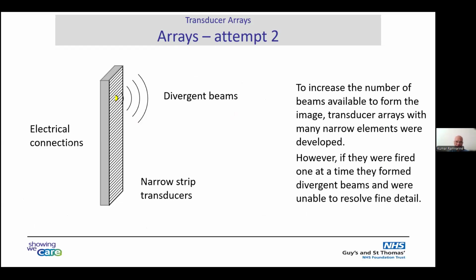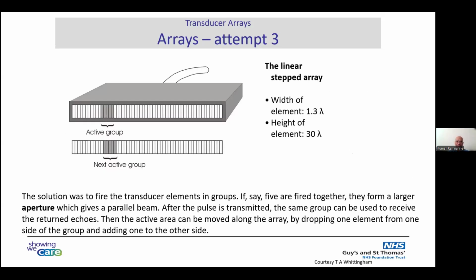So this is how modern transducers work, essentially. You have maybe 100, 200 elements, and a number of these elements are fired at the same time to produce the beam. By having a number of elements, you're able to produce a collimated parallel beam. And this allows you to produce high resolution images because as you scan across the array, you overlap the whole image plane by moving the window of the elements step by step. So this allows you to produce an overlapping B mode image, which is of high resolution. And this is how modern linear array transducers actually work.